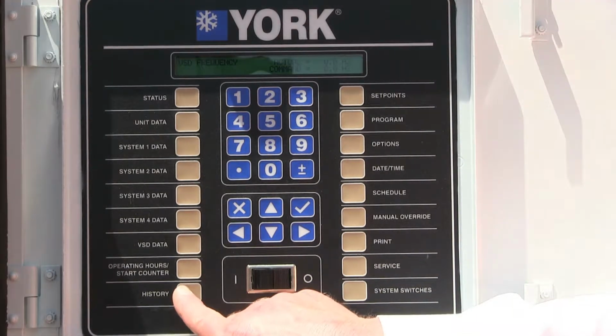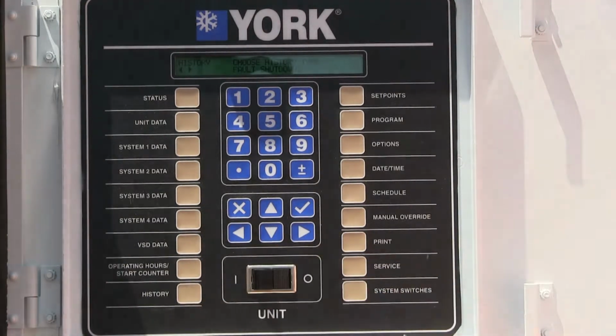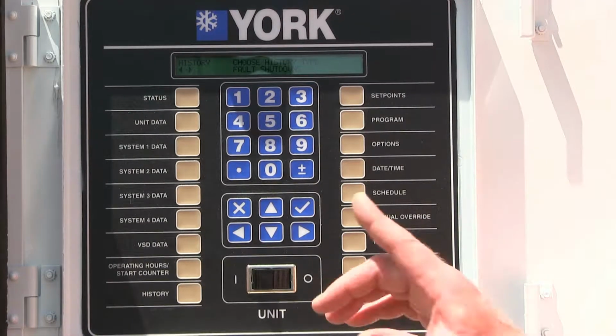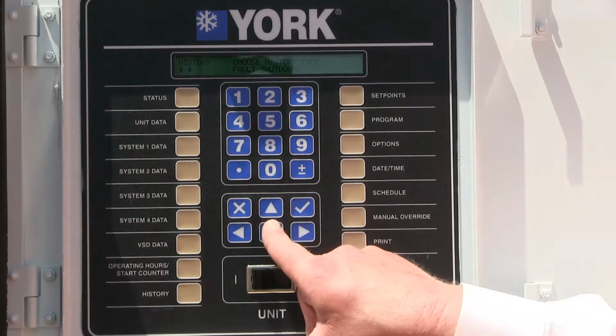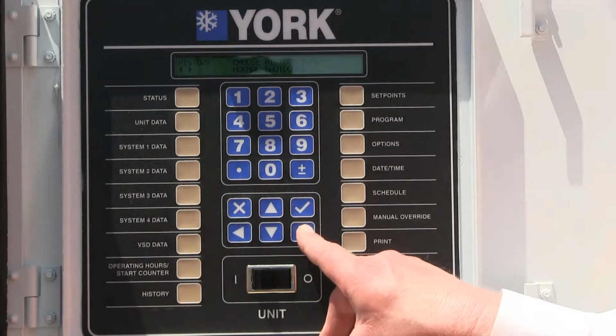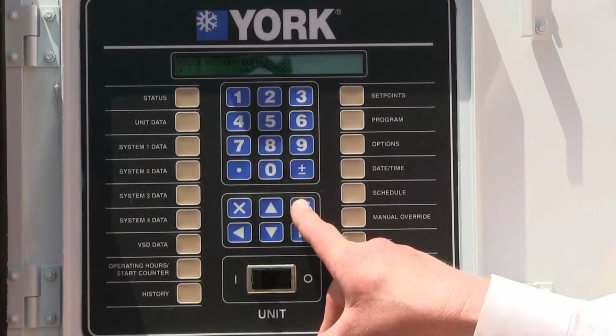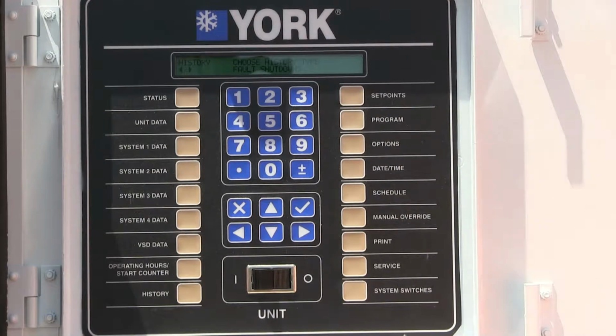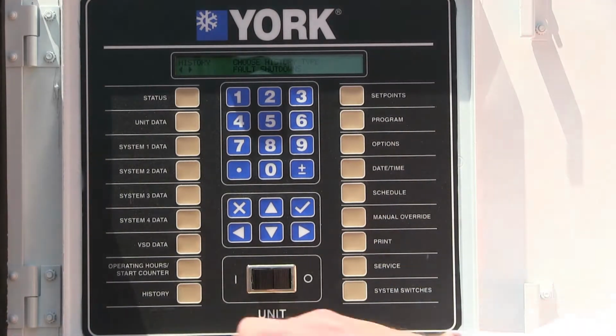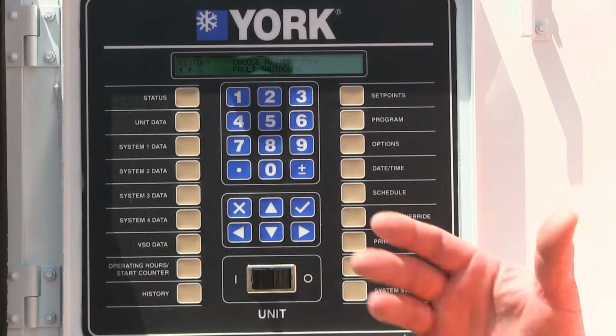The history button is very important for troubleshooting. If you push the history button and there should be a fault or a failure there, in that case you can simply go into the safety shutdowns. You go right and left on it and you go enter in there, and it'll tell you that there's no faults because it's a brand new machine. There's never been any faults in it. But should you have a fault, you would go to your history button, and that would certainly tell you where that information is.